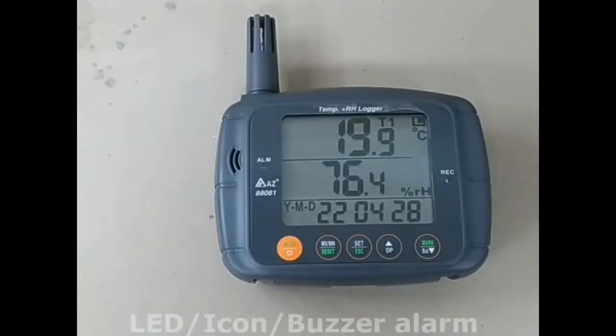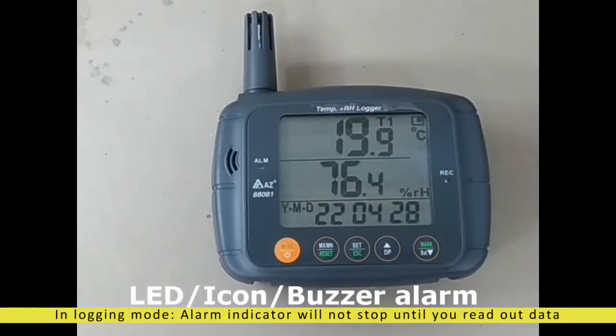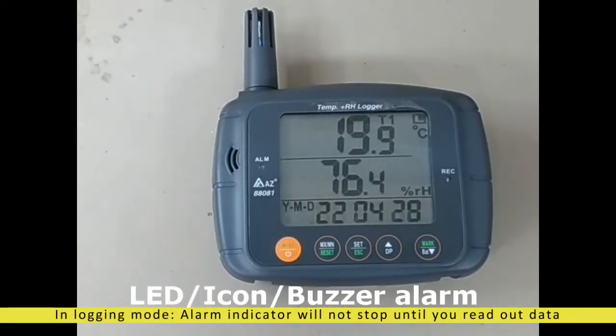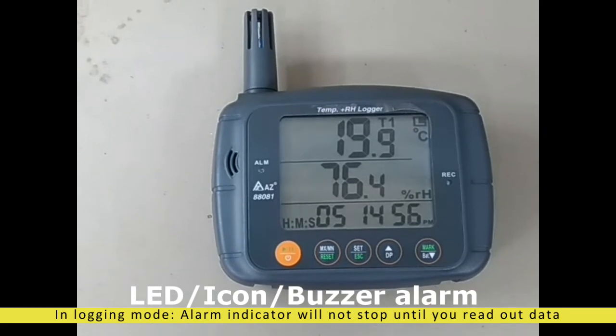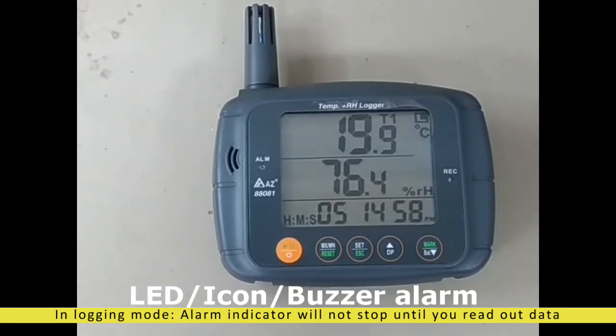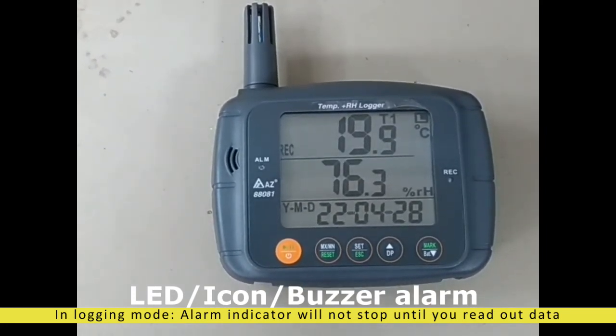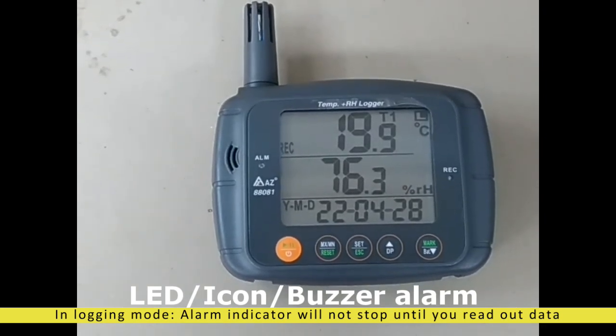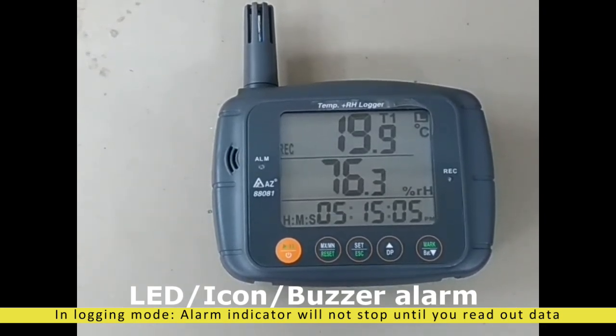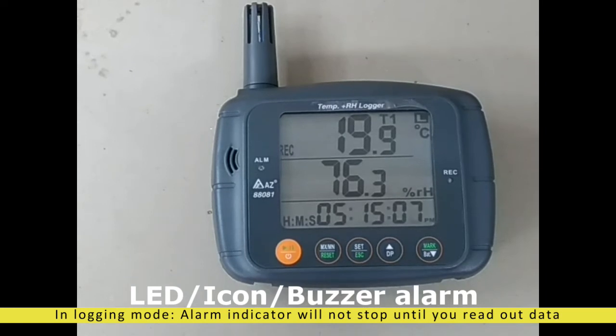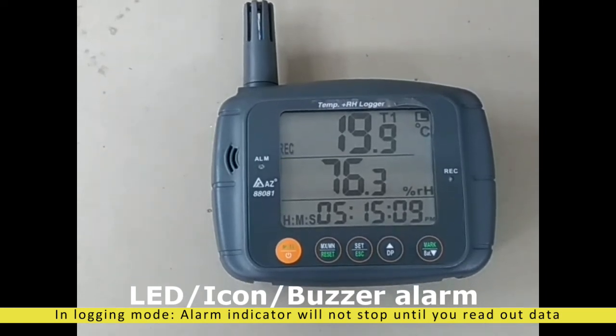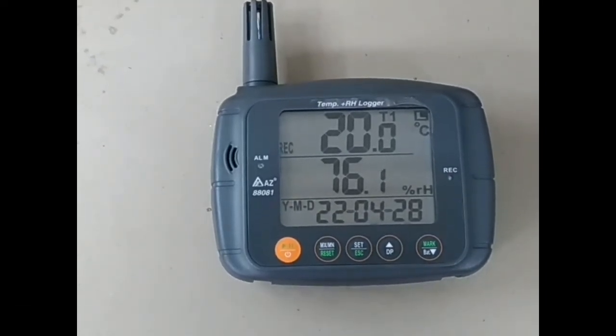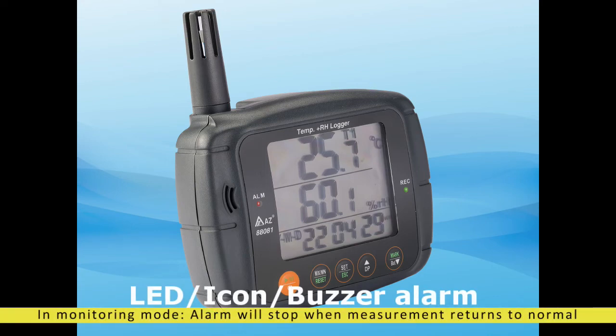While the measured value is out of threshold to trigger the alarm, the H or L icon will appear and you can hear beep sound while the buzzer feature is turned on. Alarm icon and beep sound won't disappear even when the value returns to normal range, please stop logging or download data to stop it. If it is in regular monitoring mode, alarm message will disappear while reading returns to normal range.